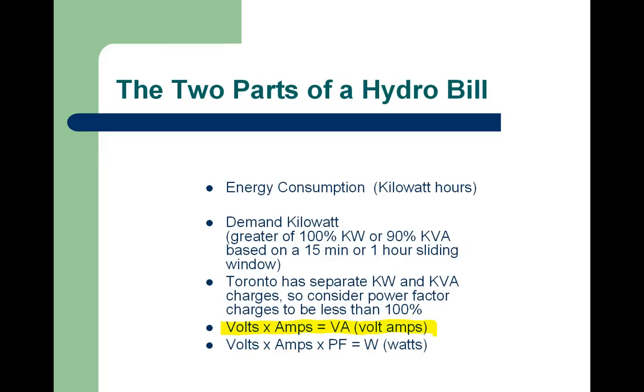Although keep in mind that the closer you get to unity or 100%, the more kVAR you require to move 1%. So in Toronto, as an example, we typically look at targeting somewhere between 95 and maybe 97% power factor, as the cost of going from 97 to 98% power factor typically is not worth the extra dollars. I've highlighted in yellow that VA or kVA is volt amps, and watts is the volts times the amps times the power factor. We'll get to that later in the presentation.